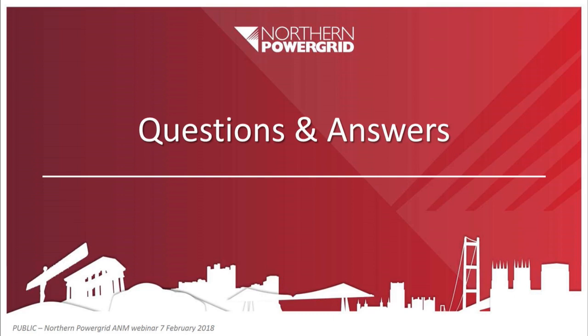So Ian, Nathan's asked us, how does active network management cope with a fault within the network, especially transient faults, maybe overhead lines, short-time faults that then release the networks intact again afterwards? So in this instance on Driffield, particularly with the overhead line network that we've got running from Driffield, the ring network, the scheme is set to monitor post-fault power flows, if you like. So the pre-fault power flows are being managed in advance of a post-fault scenario. We're looking to hold those power flows at slightly above ratings, but not to exceed a rating at any one point in time. What we're going to have is some overload protection as a backup.